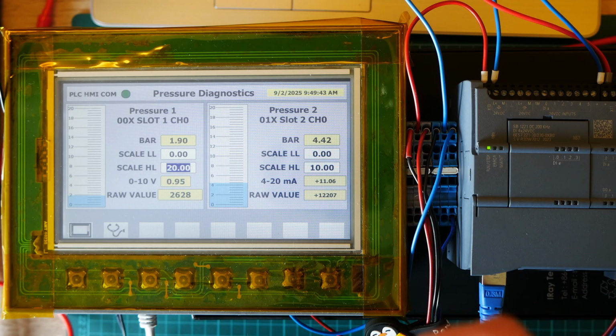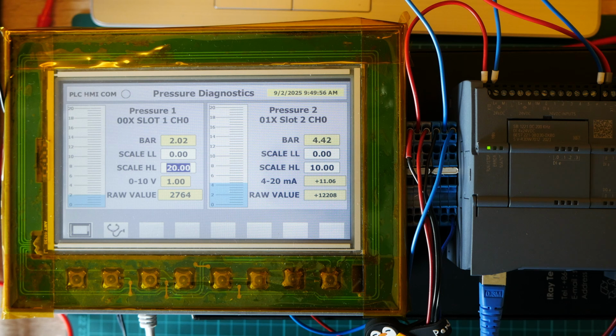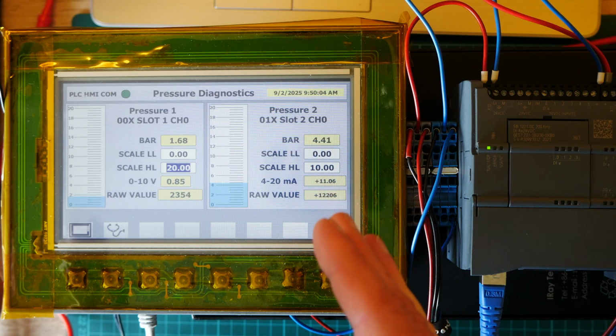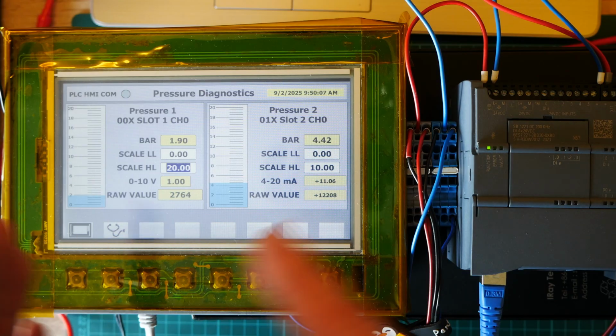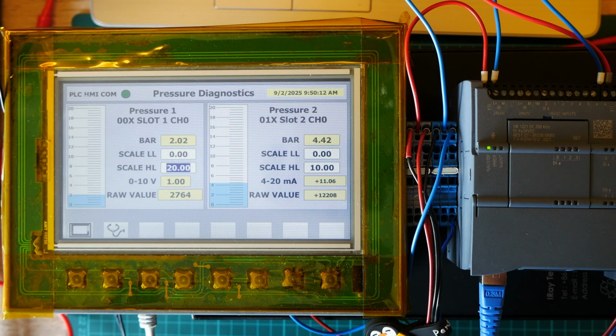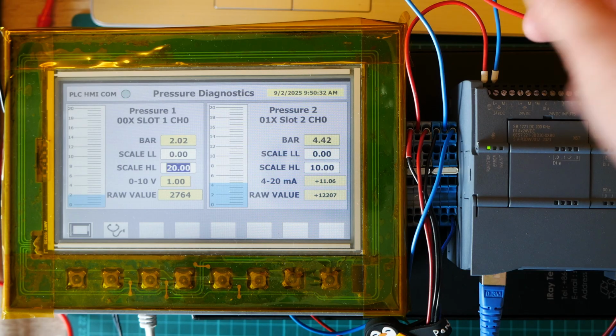Maybe put a better wire with some shielding, and shield only one side of that wire to the electrical cabinet or something like that, or remove the wire from frequency drives. And if possible, make this wire from 0 to 10 volts as short as possible, because a longer wire will get more interference. One more thing I would suggest to do, let's say you disconnect your sensor completely.